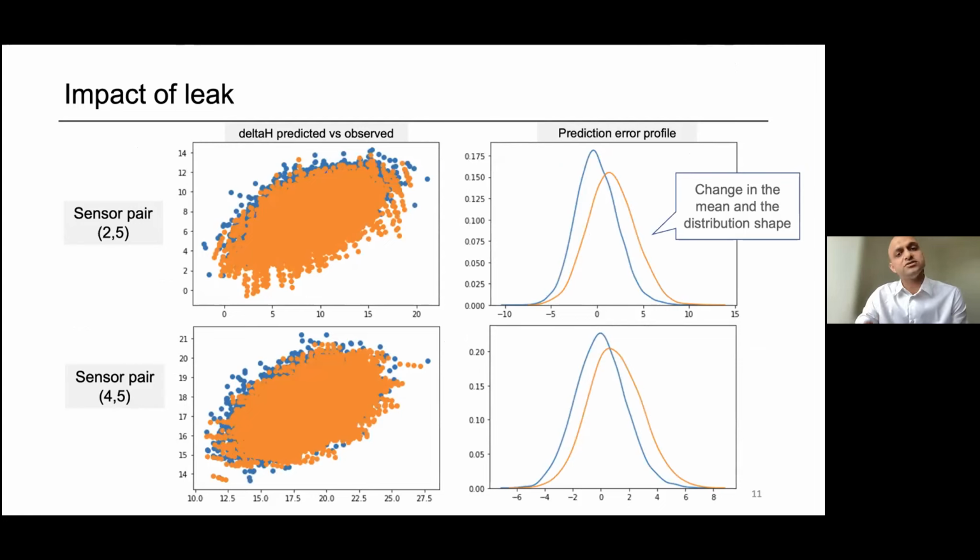Again, these are all using the software. If you want to model leaks, it's not really feasible to use a real network, so you'll have either an experimental setup or a software. So here what we observed is the blues are the one where the network is without a leak. And in this case, we had introduced a leak in one of the links.